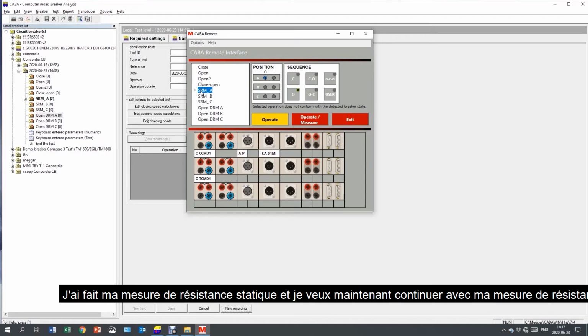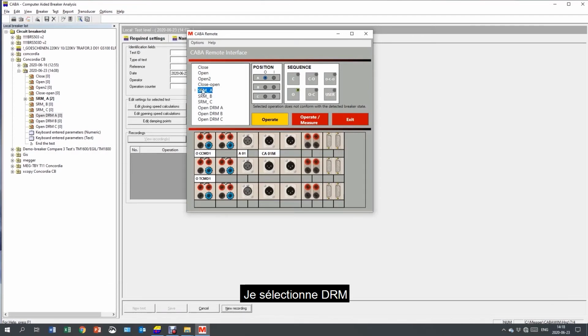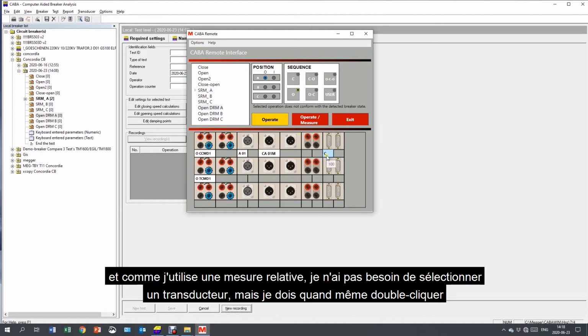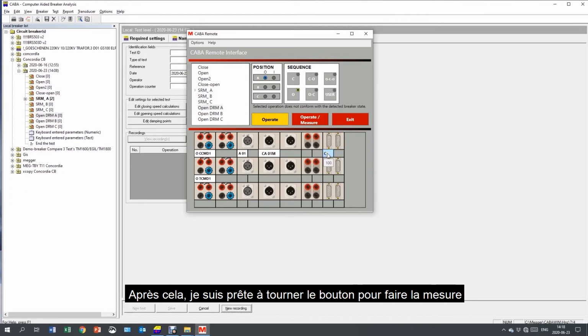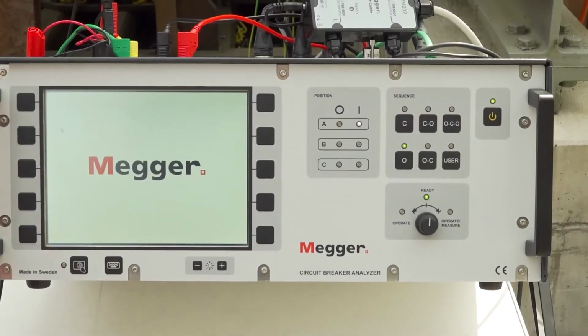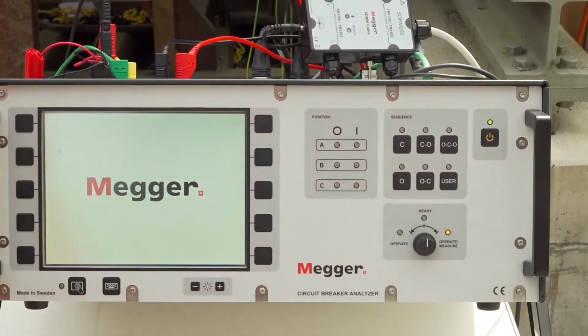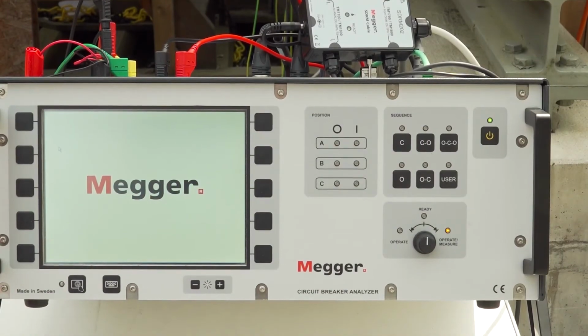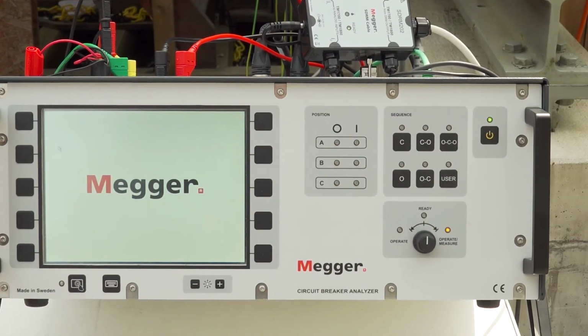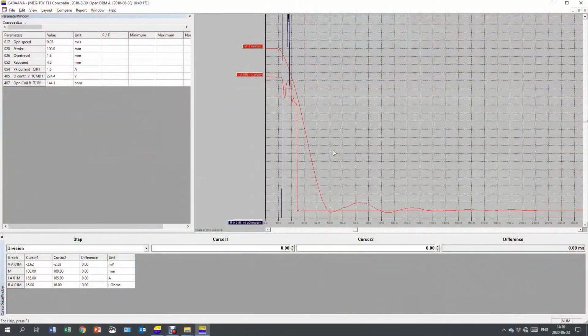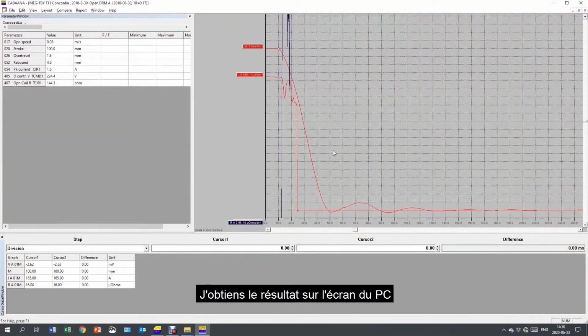I've done my static resistance measurement, and now I want to continue with my dynamic resistance measurement. I select the DRM, and I double-click on the motion channel. And I use relatives. I don't have to select a transducer, but still I need to double-click. After that, I'm prepared to turn the knob and do the measurement. I get the result on the PC screen.